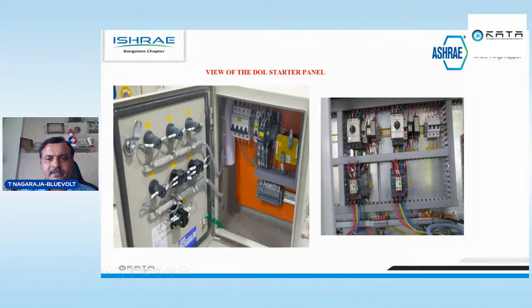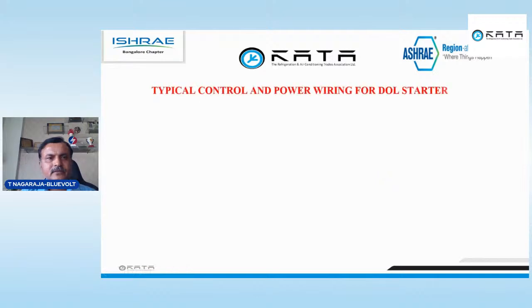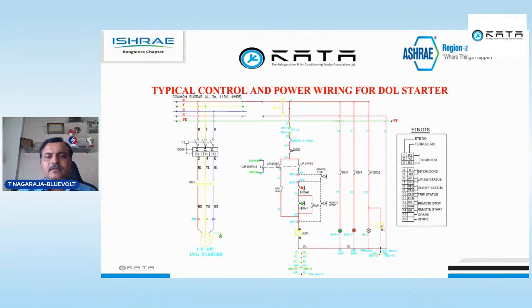For the bigger compressor, it will run directly. Here an MPCB is used. Here we have used an MCB, control MCB and timers. This is the typical DOL starter. This is the control and power wiring for the components I showed earlier. See, this is the MPCB, then the contactor, then it will go to the motor.